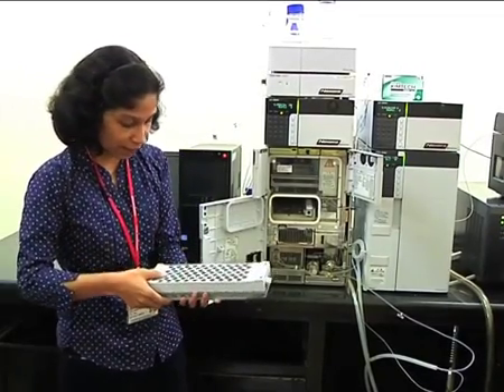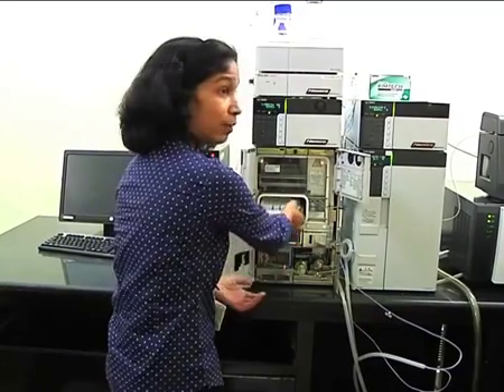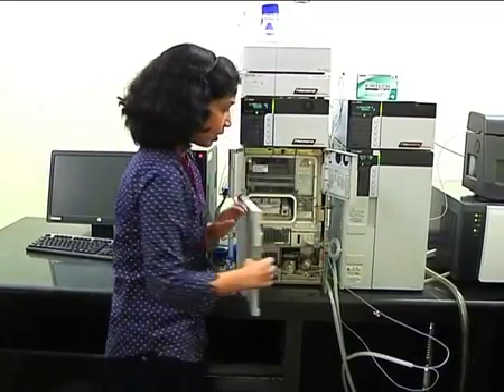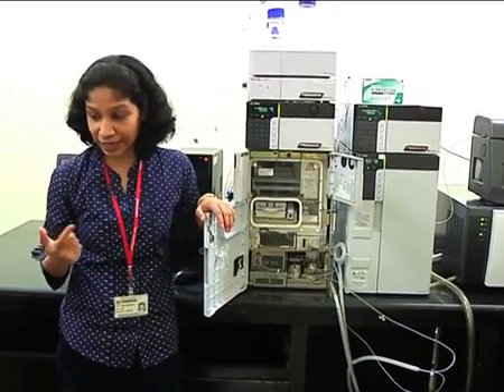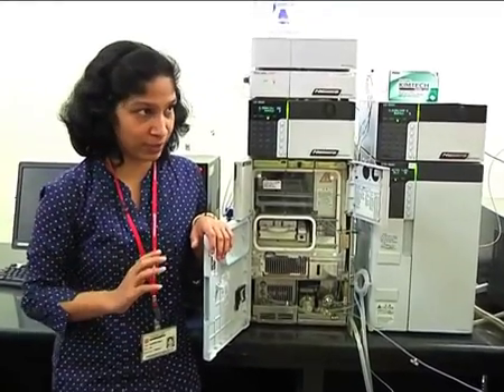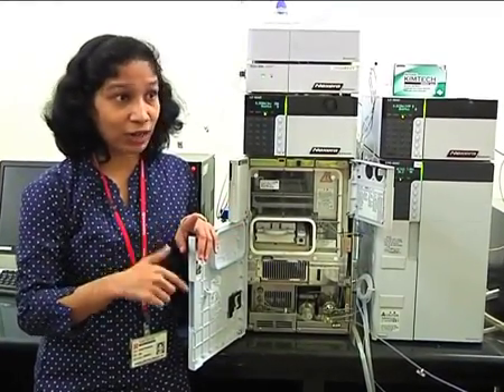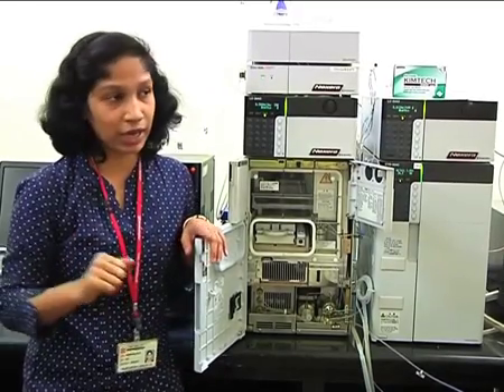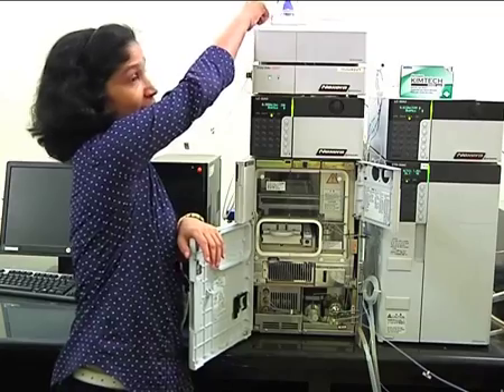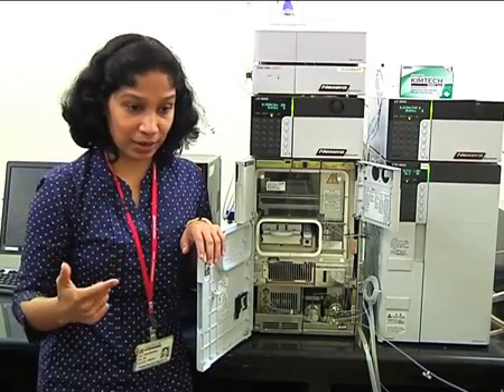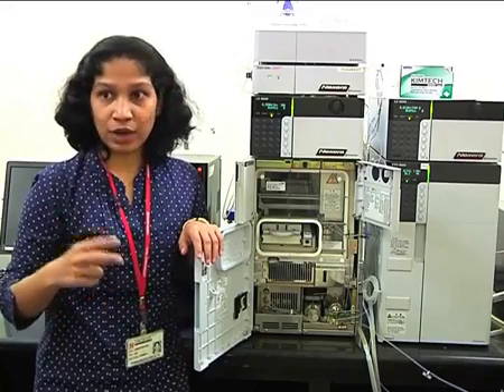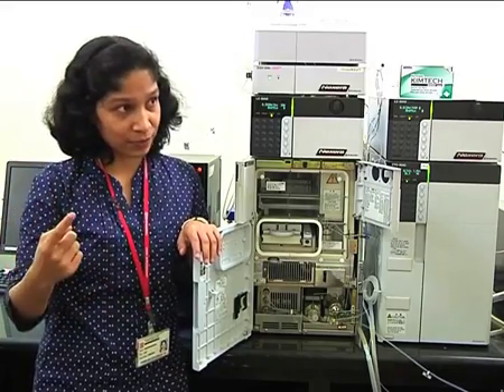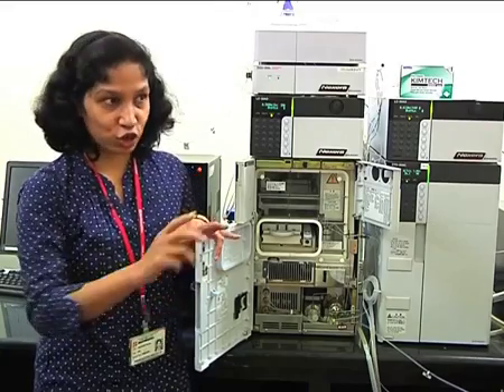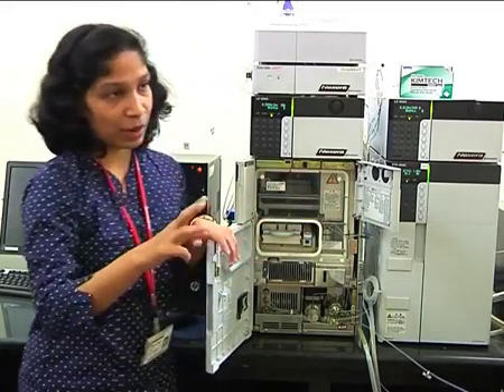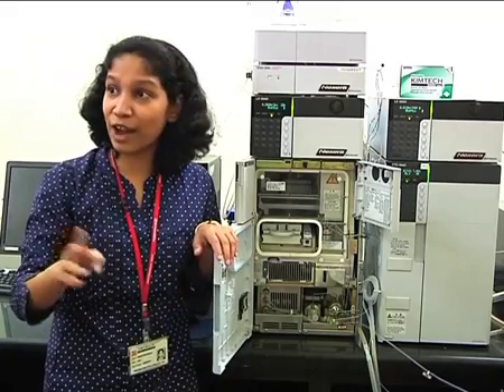Now in the case of this auto sampler, carryover is avoided by certain means. Firstly, this needle is coated with a special type of polymeric material, which does not allow anything to get absorbed on its surface. That is one way you are not allowing carryover to occur. Secondly, there is another port which is given for rinsing. So there is an option of rinsing your needle's outer surface when it performs the injection. There are multiple options. One option is called before and after aspiration.